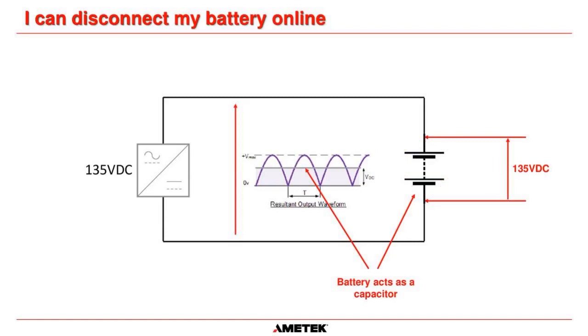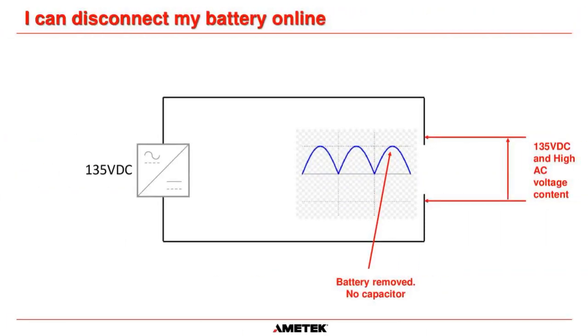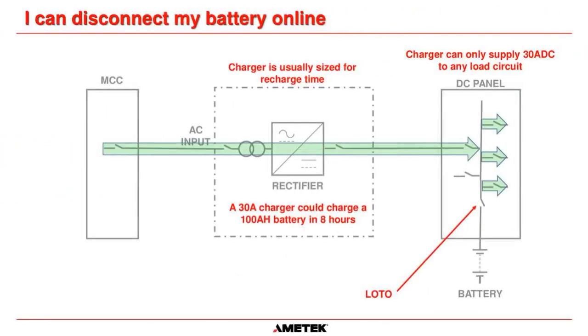But when you remove the battery, there is no capacitance anymore. So you're getting pure DC voltage, but it's pulsating DC going out to your circuits. And remember, the peaks of this DC are obviously dependent on how the SCRs are phased, but they're going to be quite high, and your load circuits don't like that. Especially for switchgear and tripping and closing systems, some of the relays will actually drop out with this form of pulsating DC going to the load circuits, and you will cause your MCC to trip. So to say that you can remove the battery out of service while you have a charger connected, in truth, you should really never do that. And here's another reason.